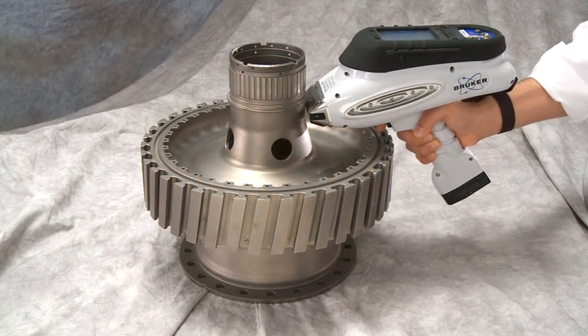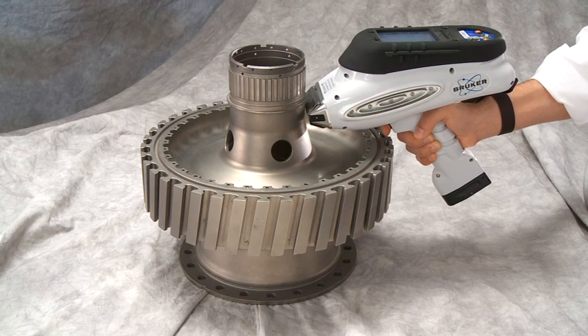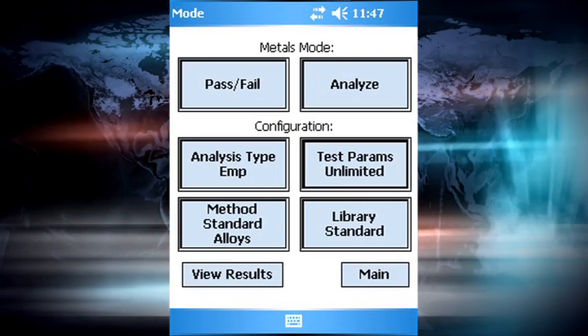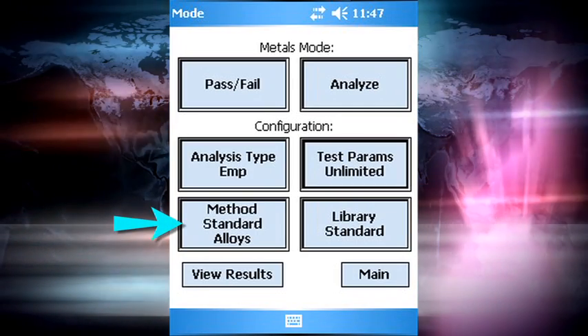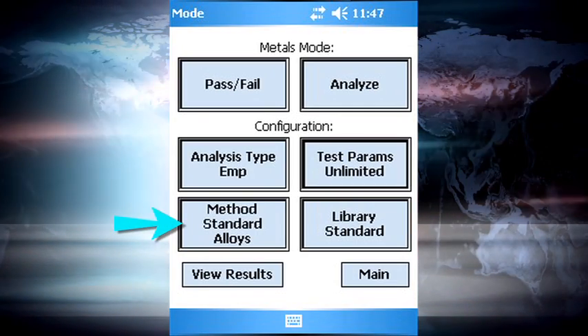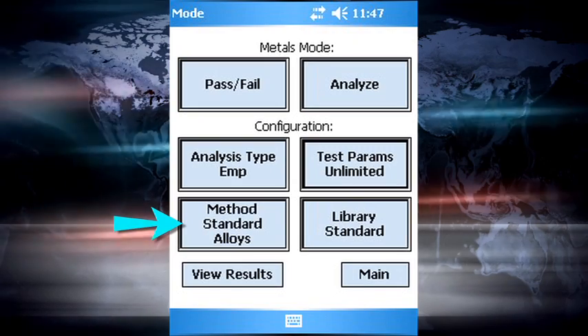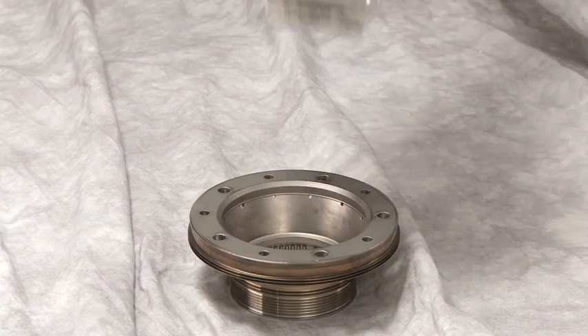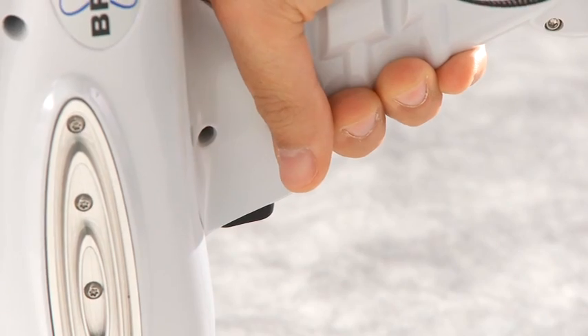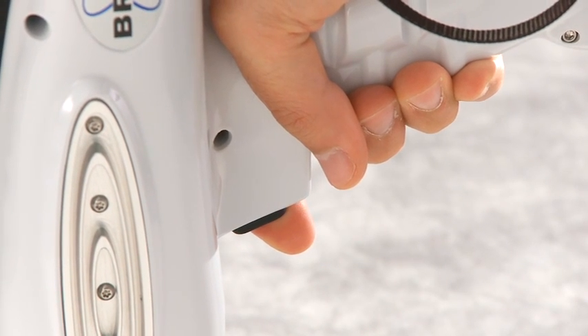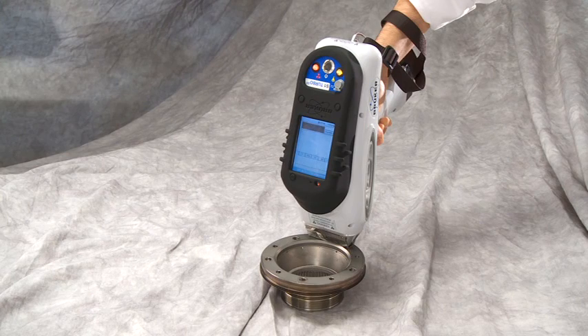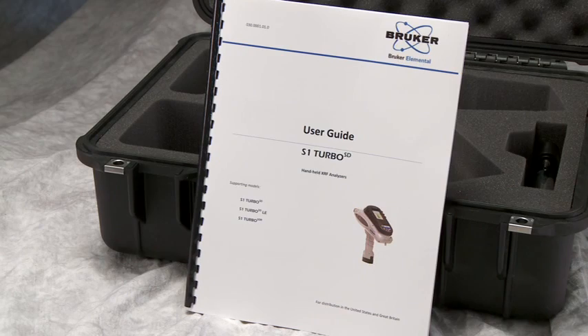The most basic type of measurement on the S1 series analyzer is a single-condition empirical calibration measurement. The empirical standard alloys calibration is the most common example of this type of measurement. The setup for this measurement is shown here. In this case, the measurement will begin when the trigger is pulled and run as long as the trigger is activated. The S1 software supports timed assay, in which the trigger does not need to be continuously activated. See the user's guide for details on this capability.